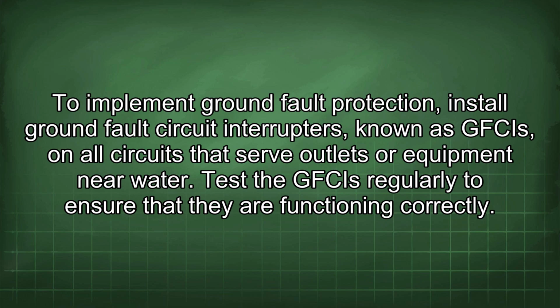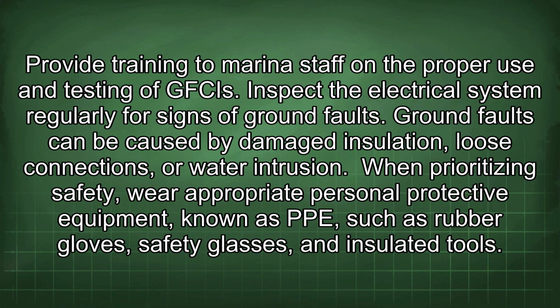Test the GFCIs regularly to ensure that they are functioning correctly. Provide training to marina staff on the proper use and testing of GFCIs. Inspect the electrical system regularly for signs of ground faults. Ground faults can be caused by damaged insulation, loose connections, or water intrusion.